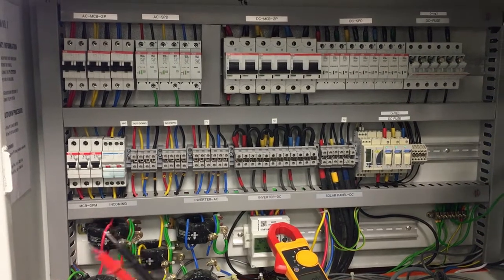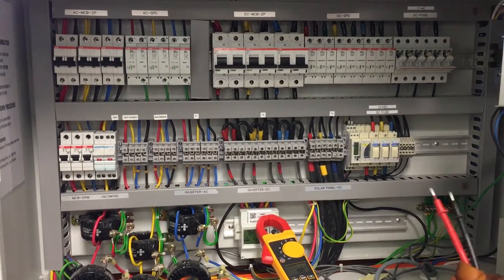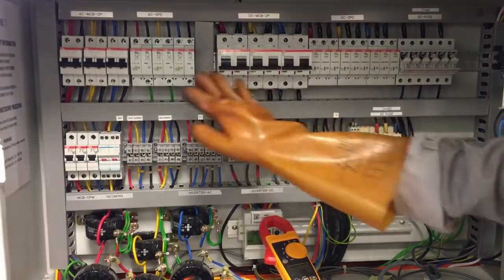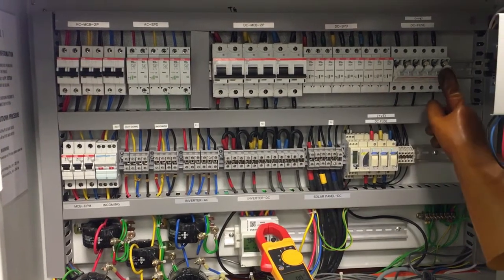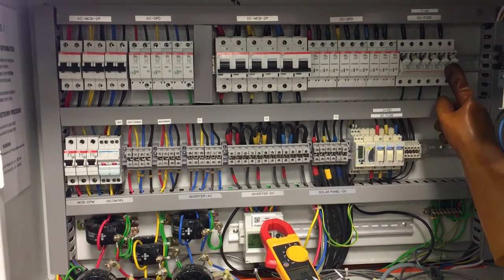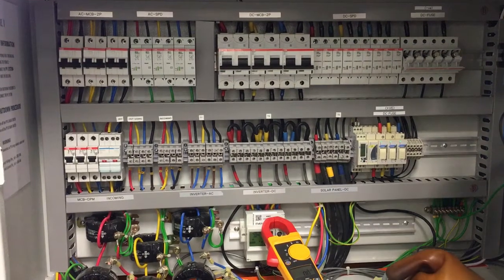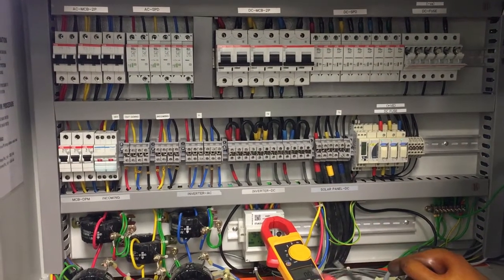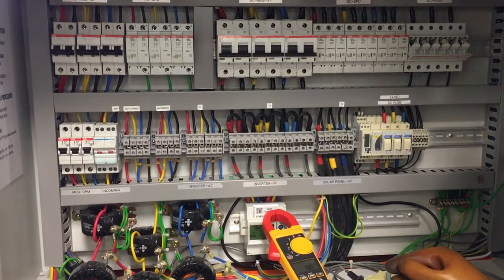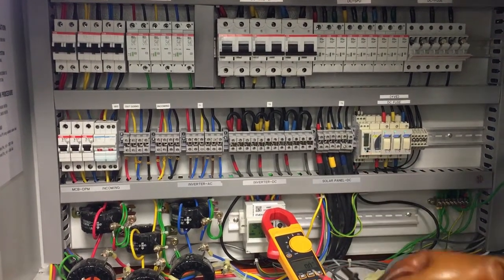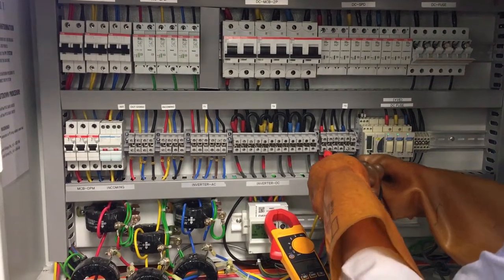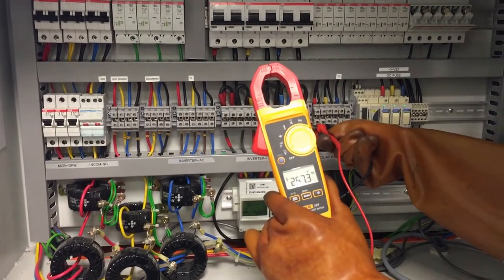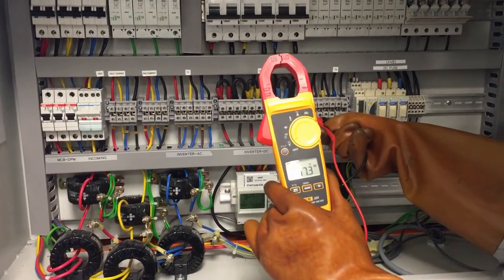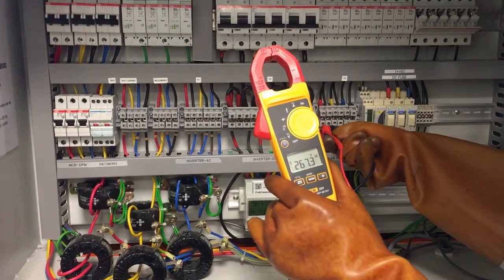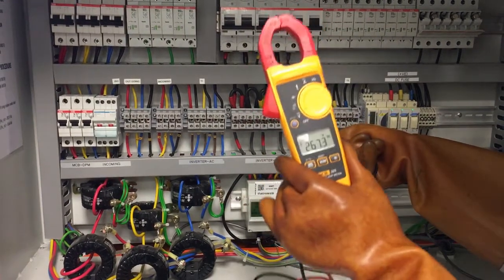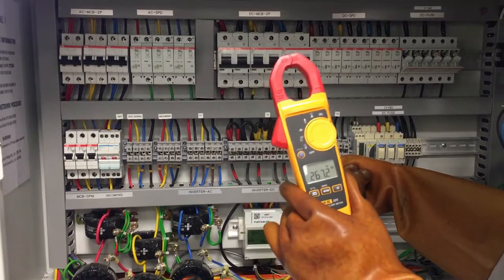Now, the condition of all the protective devices, as you can see, is off. The DC MCB is off, the AC MCB is off, and the fuse is open, meaning it's an open circuit. But we need to be careful because the supply coming from the solar panel is still energized, because I am taking this video during daytime. If I measure using this meter between positive and negative for one string, you see that the voltage given is 267 volts for one string, for one inverter. So we need to be careful that even though we have turned off the system, there is always going to be live voltage coming from the PV, as long as there is sunshine.